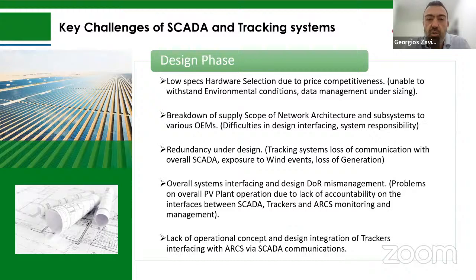The redundancy concept of design is also a very important challenge, especially with the tracking system, where loss of communication over the SCADA exposes the system to wind events, but is also responsible for loss of generation. We have seen designs where, from either the SCADA network architecture or the tracker communication system design, there is an under-design of redundancy that has a huge impact from the developer's point of view during the operation phase.